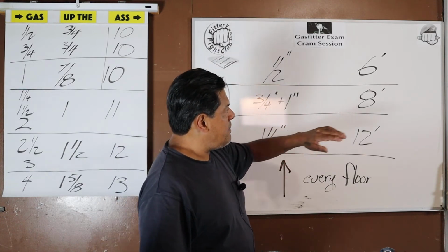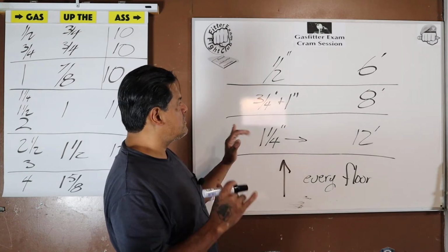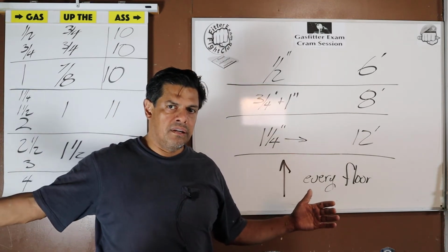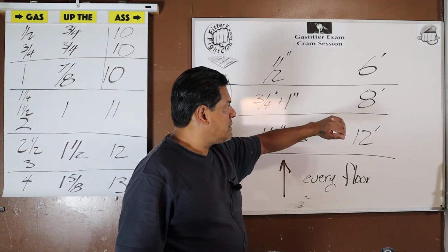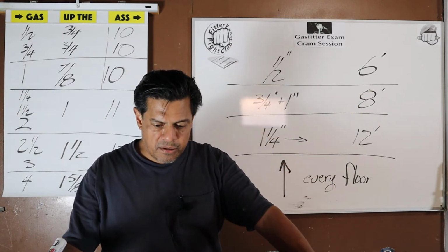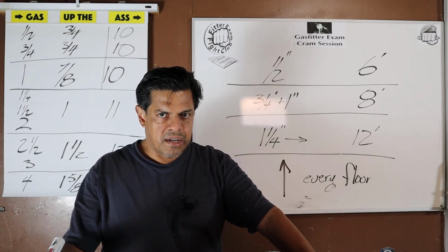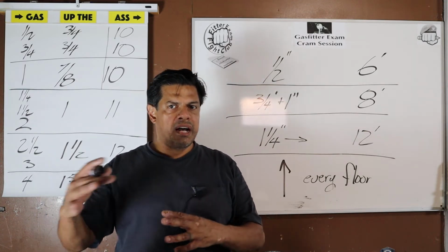And how wonderful for us it shows up here because that's a number we need to remember. And now 8 we're going to remember. Not only is it the interval for our hangers for horizontal 3/4 1 inch, it's also the size at which we're going to purge no matter what the linear footage of pipe we're dealing with. So that's another way to remember it because now 8 does work. I always like to make my numbers do a lot of work. One number triggers a lot of information for me. A lot of stuff gets tied together even if it's not directly related by a number.